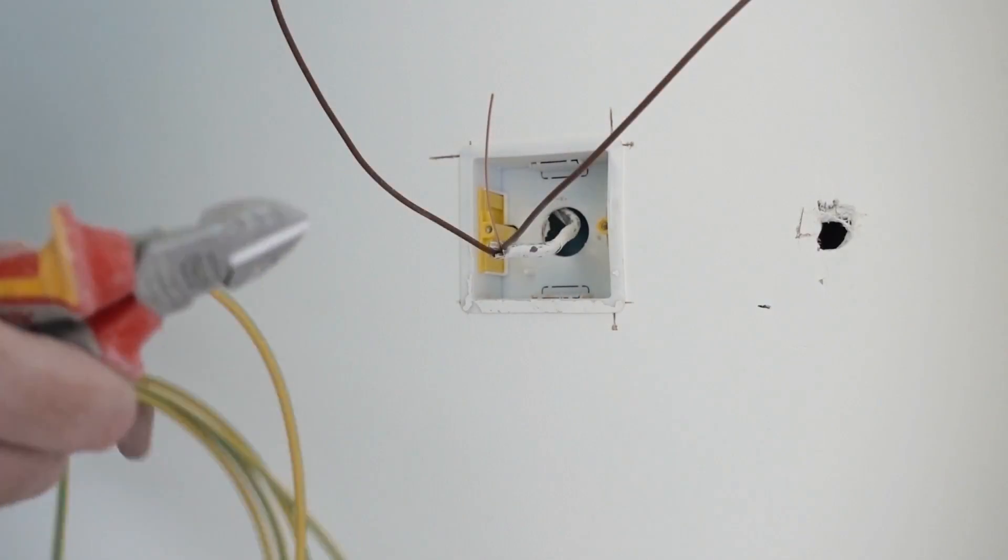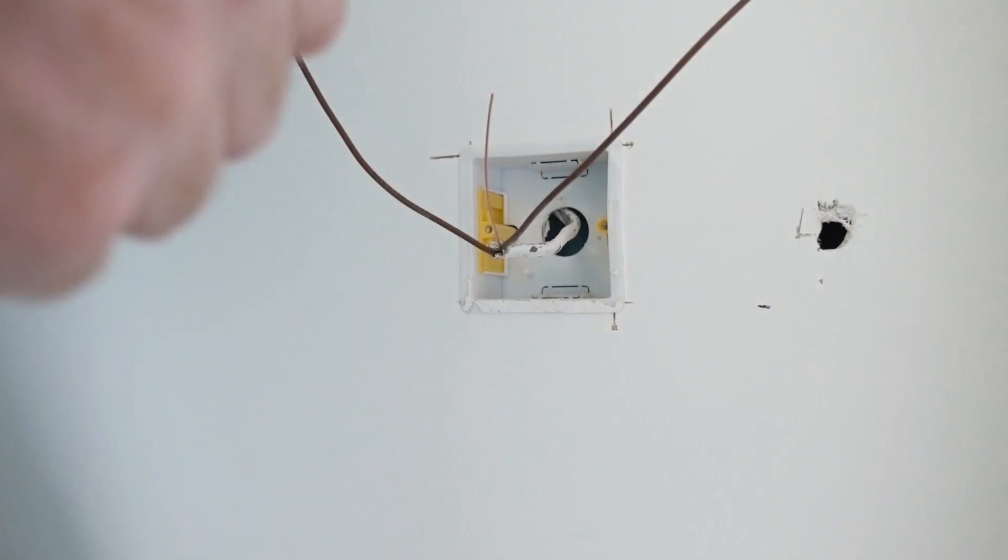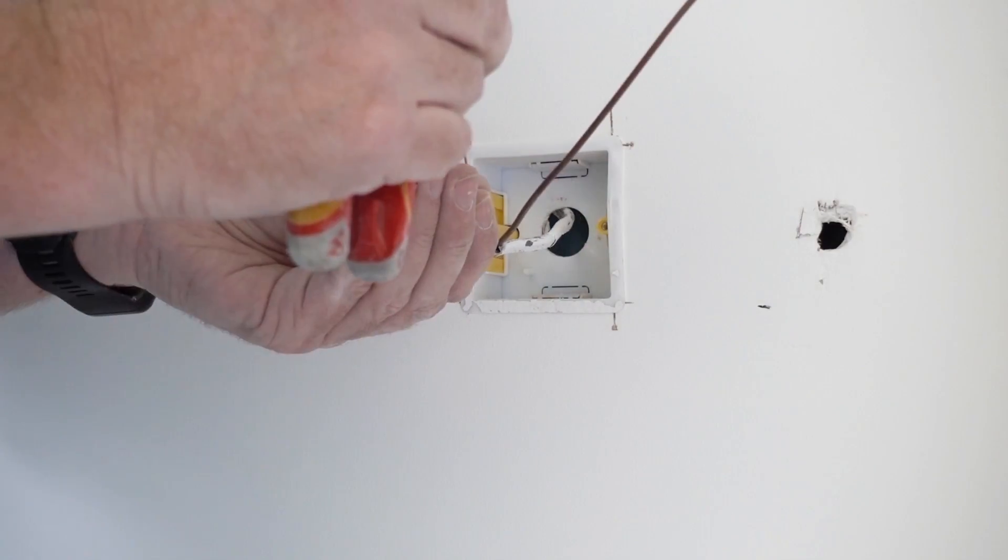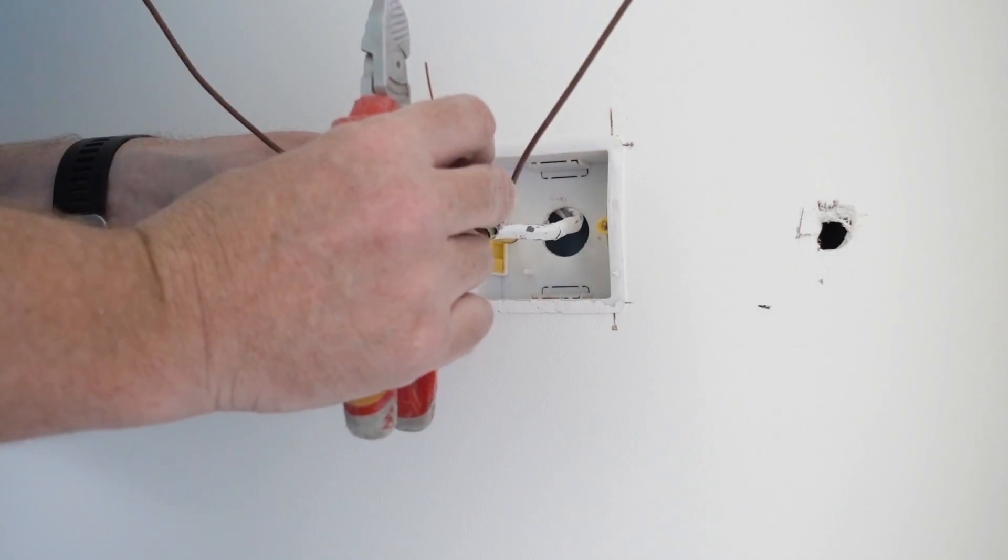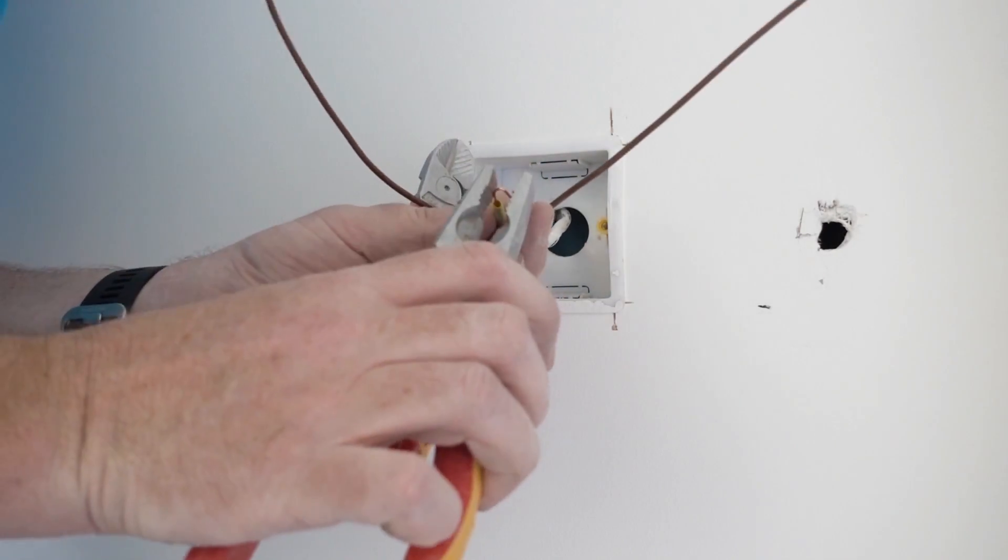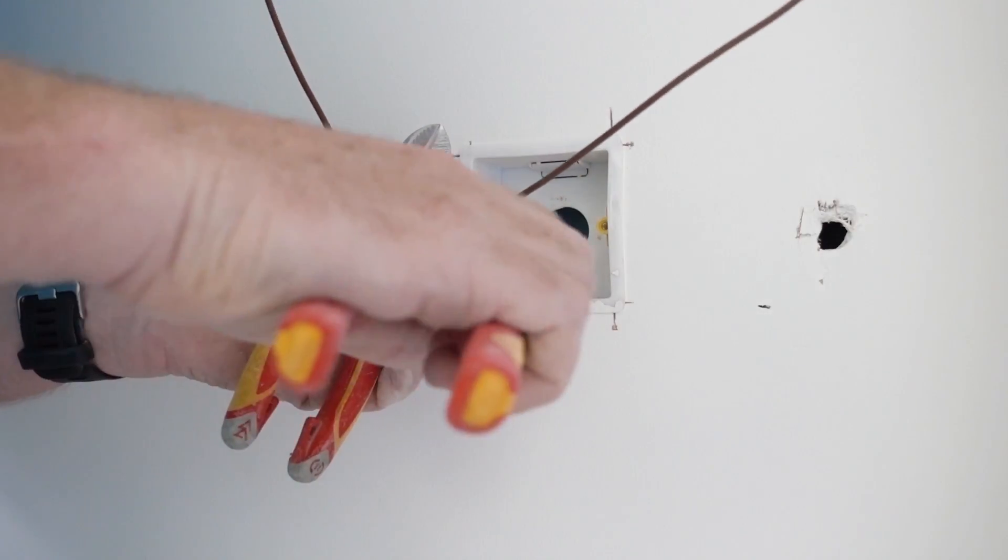Right, now with the earth wire, I'll just cut it shortish there and get a bit of earthing sleeve and put it over there. Now if this was a metal back box, the earth would just connect into the terminal on the metal back box, but because this is a plasterboard back box it doesn't have one.